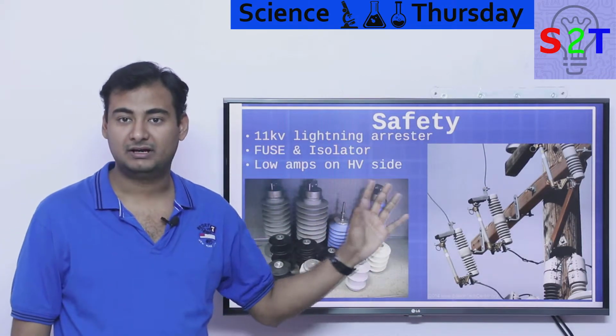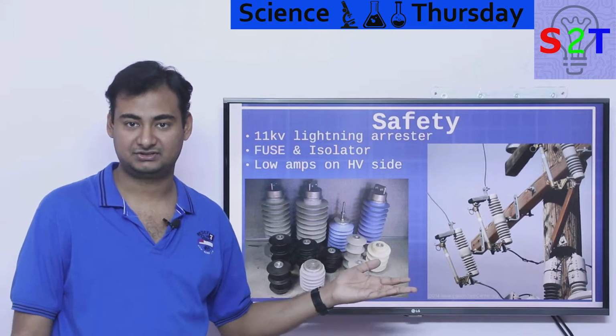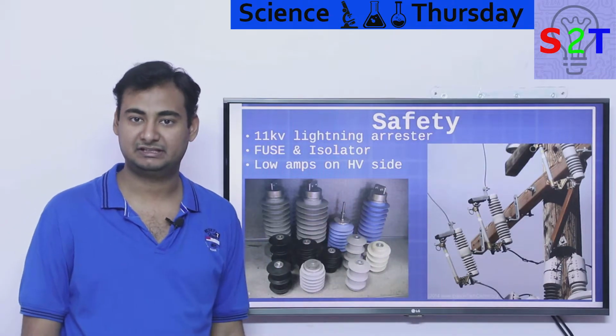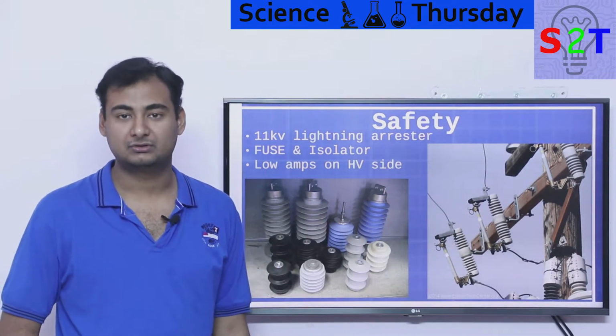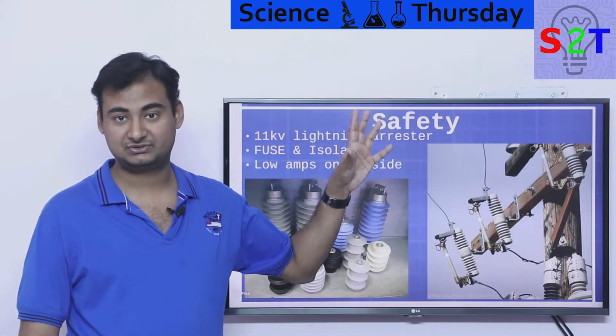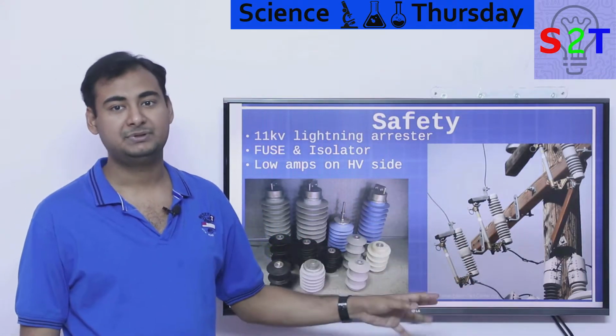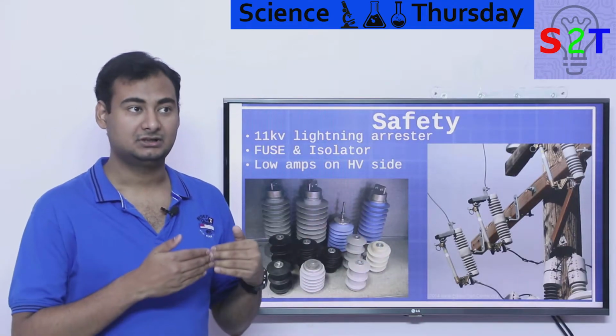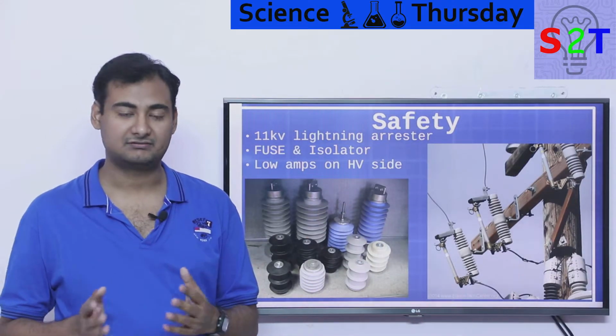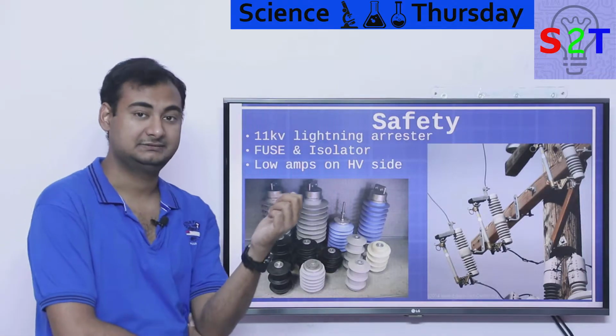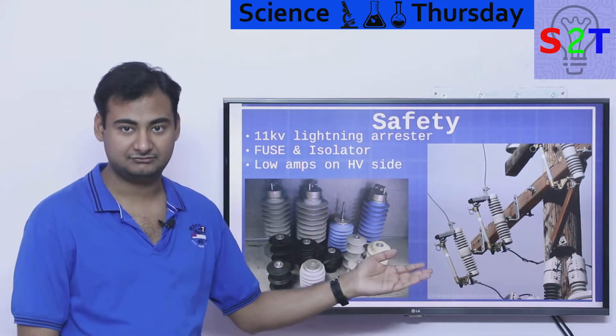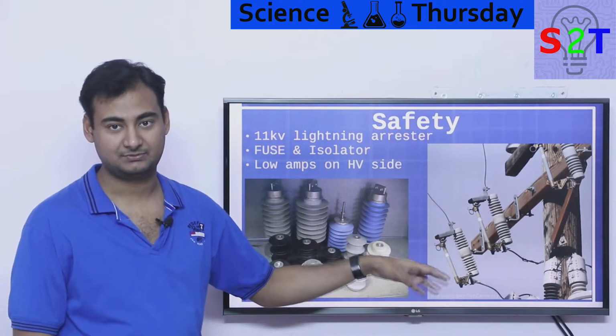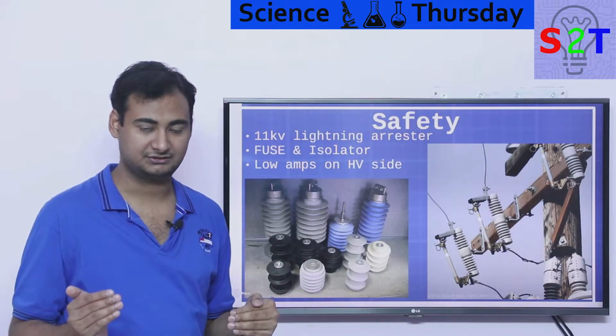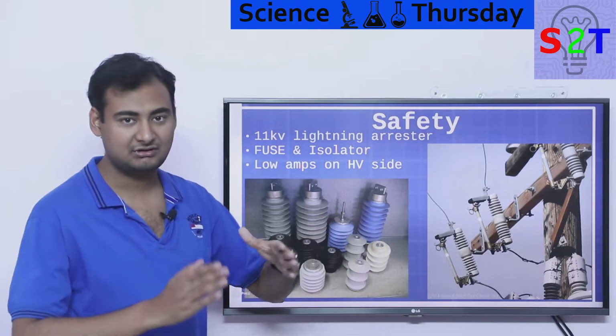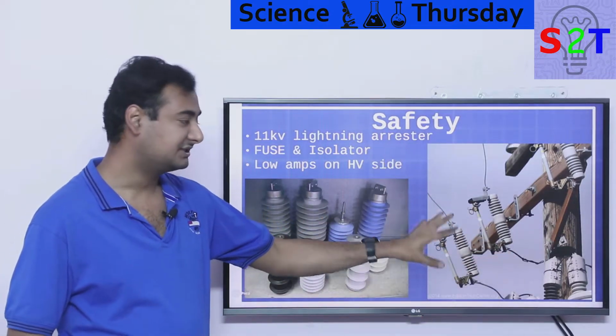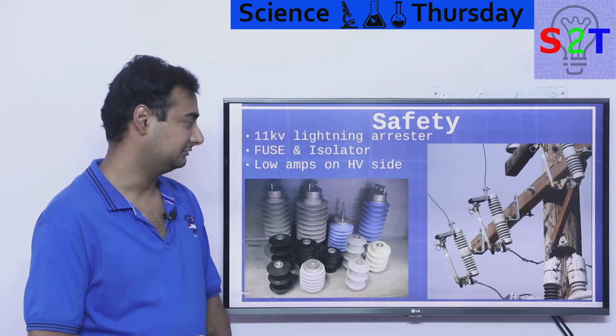And then you have to understand why the heck we put fuses on high voltage. Why are we putting fuses on an 11 kV line when we can buy a fuse for 200 or 240 volts? On this line, which is powering a transformer, the amperes are what affect the fuse. You want to keep the ampere rating low, otherwise your fuse will be very expensive. To compensate for that, we generally put it on the high voltage side, and we figure out how to manage the voltage, because higher ampere is very hard to handle because it melts things. With high voltage, you just have to make sure it's far apart. So that's why we put high voltage fuses.